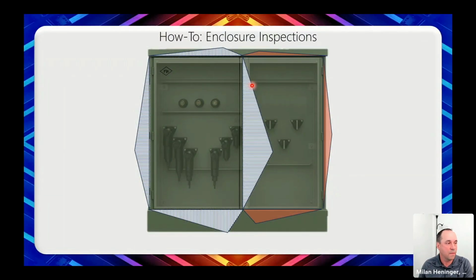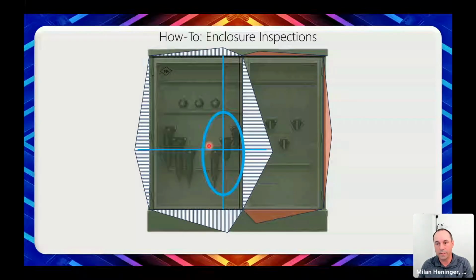Based off this information, we can kind of triangulate where the issue is. And based off that information, I could be quite confident that we need to go look at these bushings or these T-bodies to figure out what that specific issue is. I may bring in other tools, I may bring in thermography, I may go in and do a clean and inspection by shutting everything down. There are things we can do, but being able to make this kind of precise diagnosis with the door closed is really helpful in determining not only what the fault is, but what other tools and technologies we can apply to understand and solve that problem.